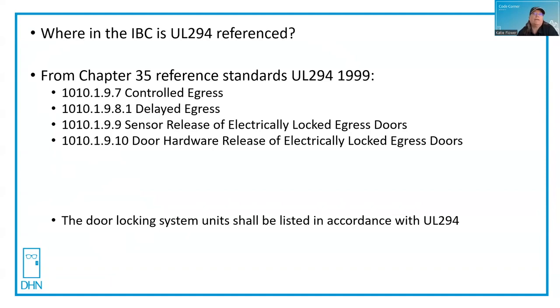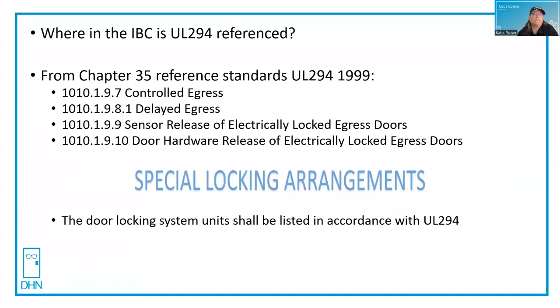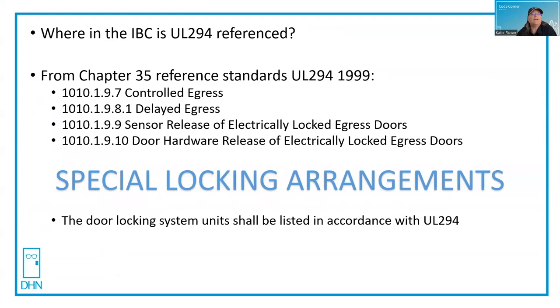What do these all four have in common? They're typically using some kind of a mag lock or an electrified lock that locks the door on the egress side. In other words, these are special locking arrangements. The door locking system units shall be listed in accordance with UL 294 — every one of these has that as a listed criteria, so the door locking system units are what needs to comply.